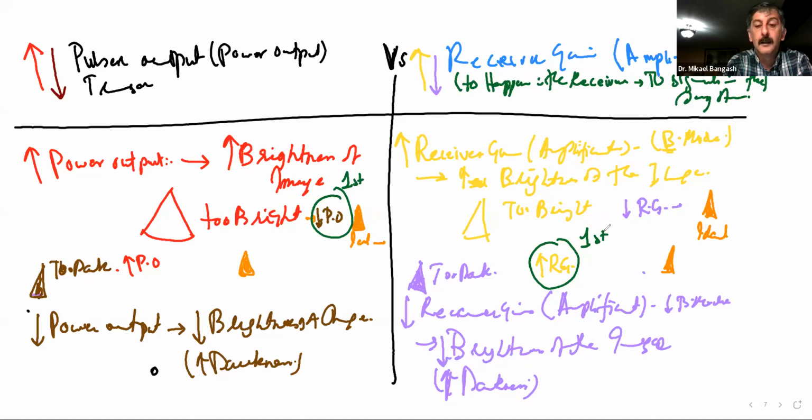How do we do that? Mainly by turning the B mode knob clockwise. But ladies, it is all a matter of tuning. Because if you keep on amplifying, at some point you may end up getting more noise. So that may be the point where you say, maybe this was too much amplification. Let me just try to increase the power output a little bit.